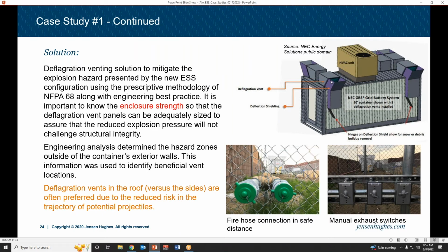So we put deflagration vents on the ceiling, so in case there's ever an explosion, it can be vented upwards, not at somebody—just send the fireball into the sky. They have a fire department connection at a safe distance. You kind of don't want to have this in line with that door, even though we have deflagration vents on the ceiling—maybe the engineer screwed up and didn't size them correctly, and that door still blows toward somebody. So you'd want the fire department connection perpendicular to that longitudinal line.